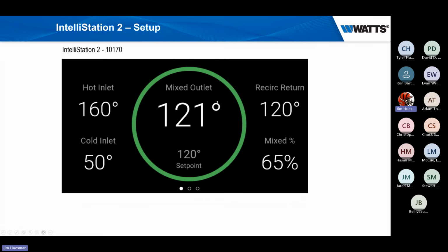So if you want just a standard mixing valve, we're set. If you say, hey, I want more features, I really want this thing dialed in, we can add additional sensors on our hot and cold return line. What's really nice is they've taken that sensor and made it not just for temperature or pressure - they've dialed it in so each sensor reads both pressure and temperature at the same time. So we only need 4 instead of having you guys order 8.